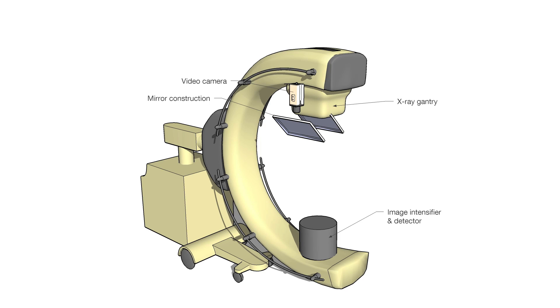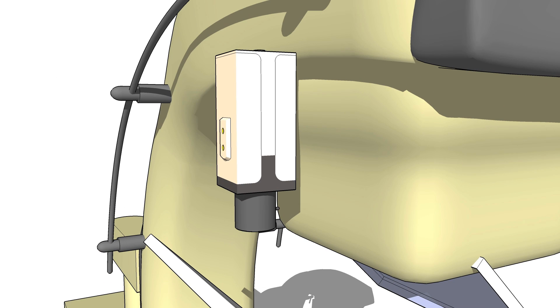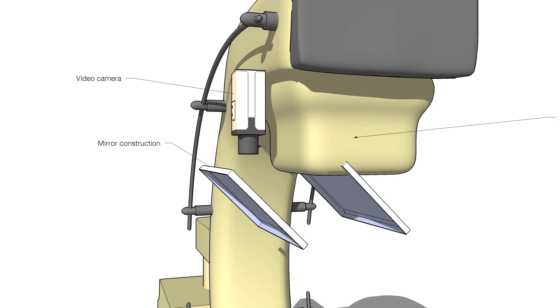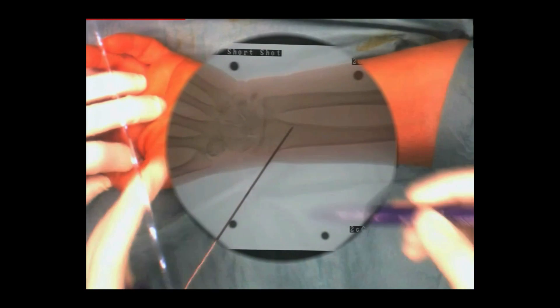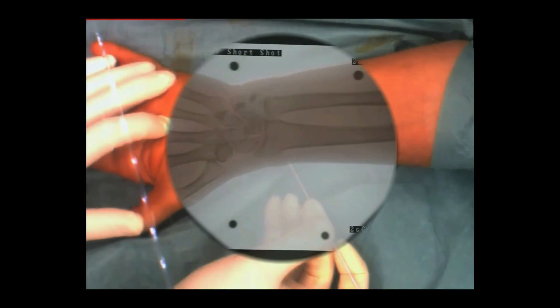CamC is a mobile X-Ray device enhanced by a video camera placed closely to the X-Ray source. Using a mirror construction, the video camera has the same view on the patient as the X-Ray device. Blending together both the X-Ray and the video, the surgeon can see them co-registered in one image, with live video information and internal structures from the X-Ray simultaneously.